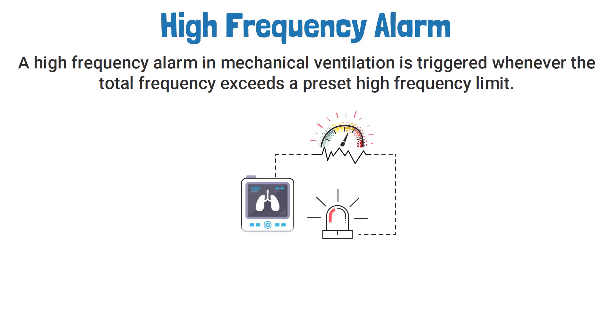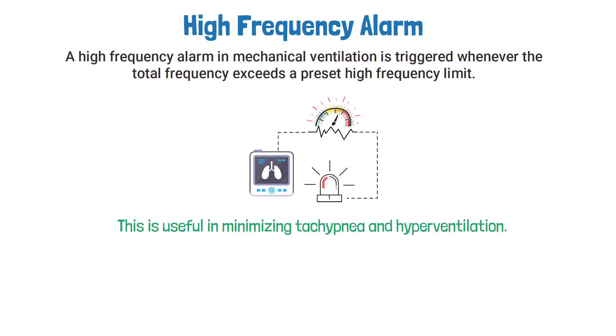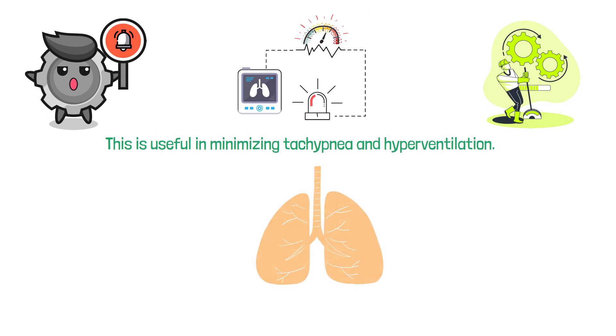A high frequency alarm in mechanical ventilation is triggered whenever the total frequency exceeds a preset high frequency limit. This is useful in minimizing tachypnea and hyperventilation. The activation of this alarm can occur whenever auto-triggering is present due to an incorrect sensitivity setting, or it can be a sign of respiratory distress.